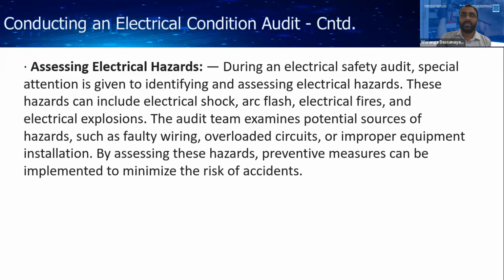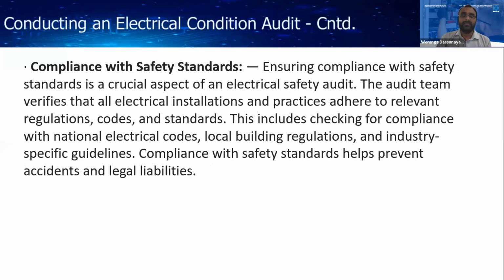Then you can assess the electrical hazard. That means you can identify whether there is a risk of fire, or whether there is a possibility of short circuit in the system. That kind of electrical hazard, or whether there are exposed parts, exposed conductors in your system. Because if someone touches that exposed conductor, he might get an electric shock. So this kind of electrical hazard you have to assess, and also include it in that report. Then you have to check whether these installations are compliant with safety standards.